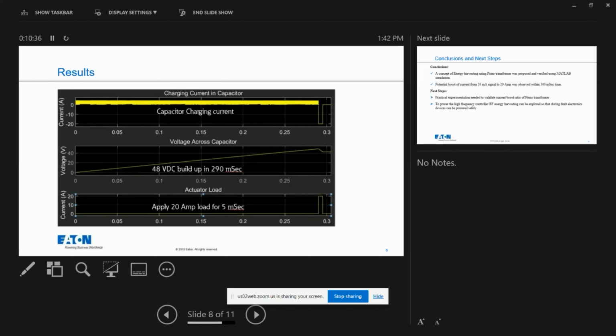The third graph shows that after 290 milliseconds, as soon as 48 volts is built in the capacitor, we applied a load of 20 amps for 5 milliseconds. In the second graph, you can see that when the 20 amp load is connected, there is a slight drop in voltage, from 48 to 45, but that is acceptable. The actuator is still able to work with that voltage.